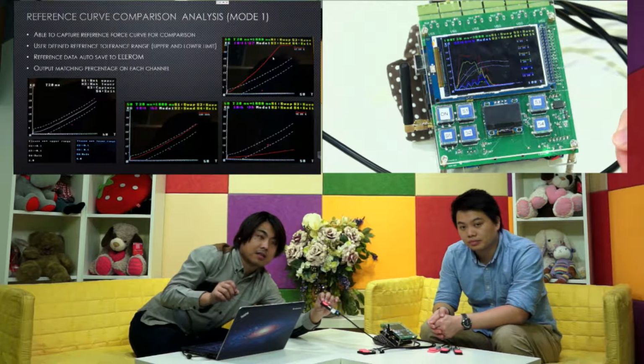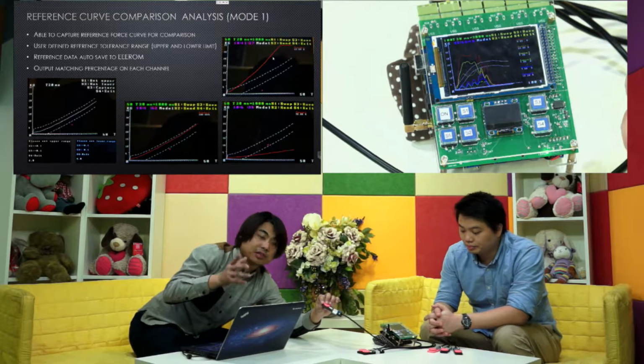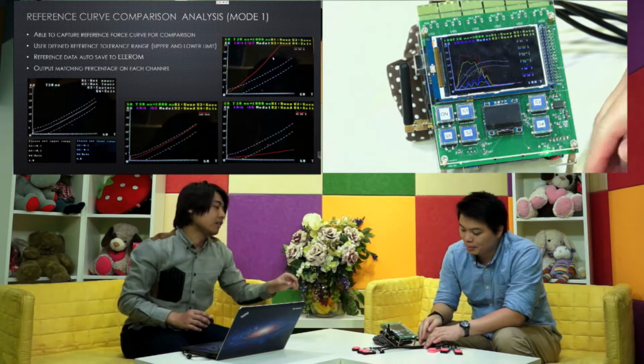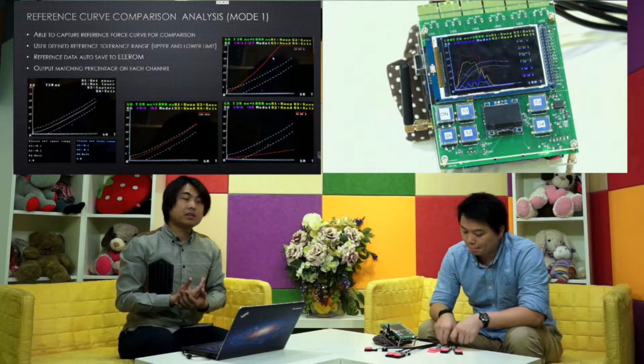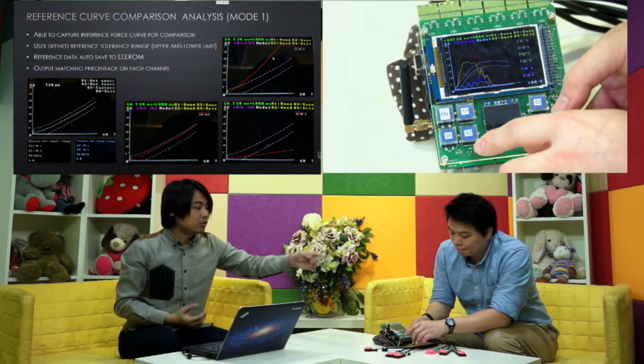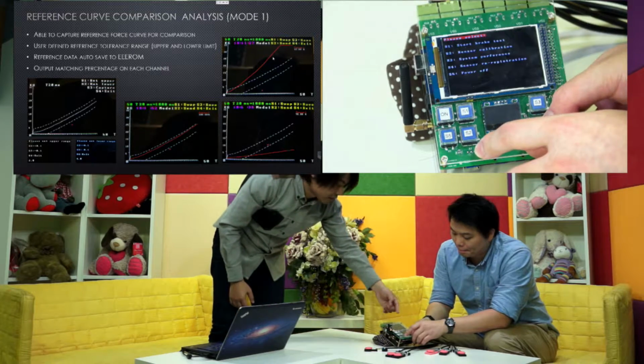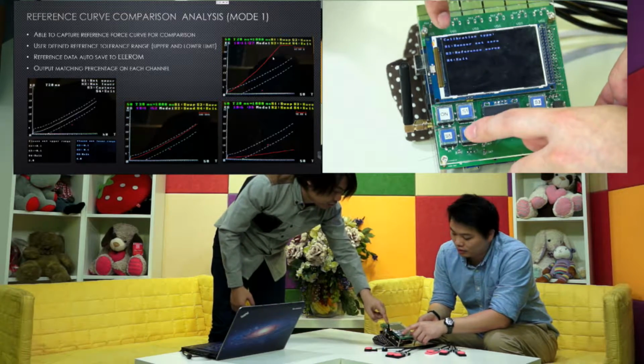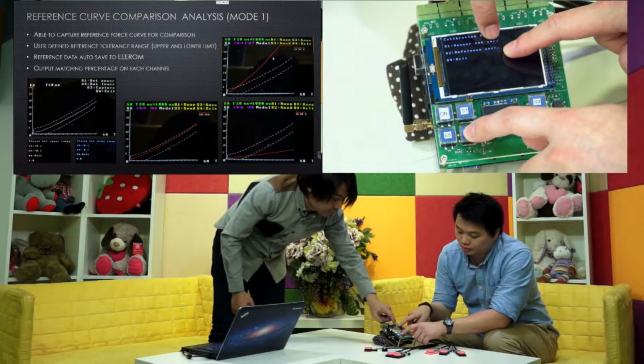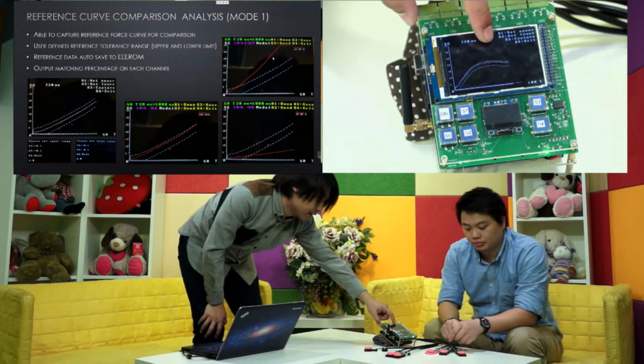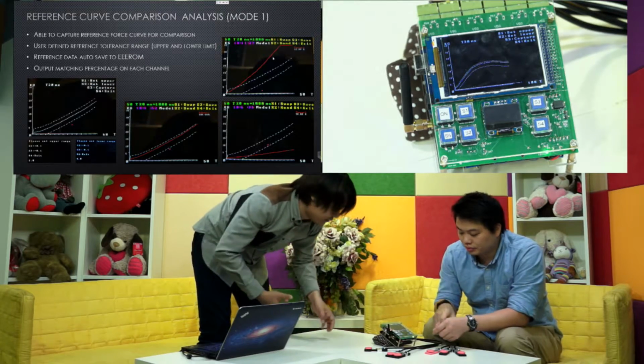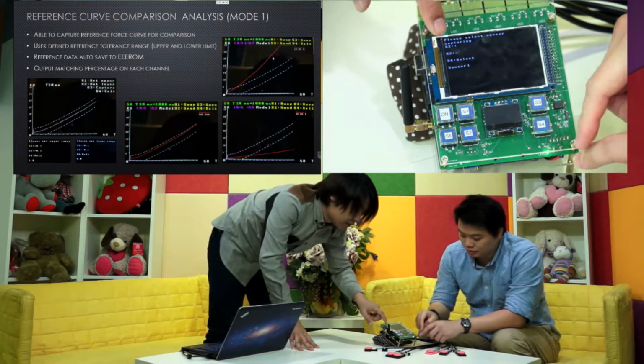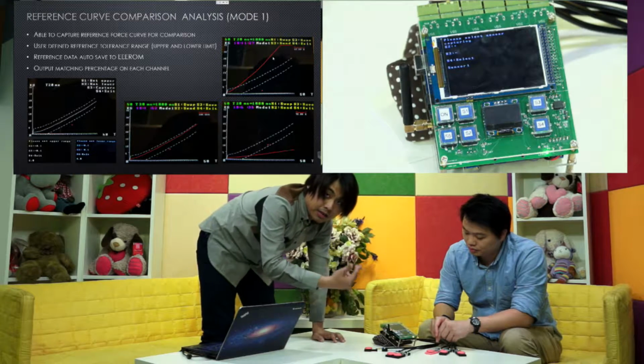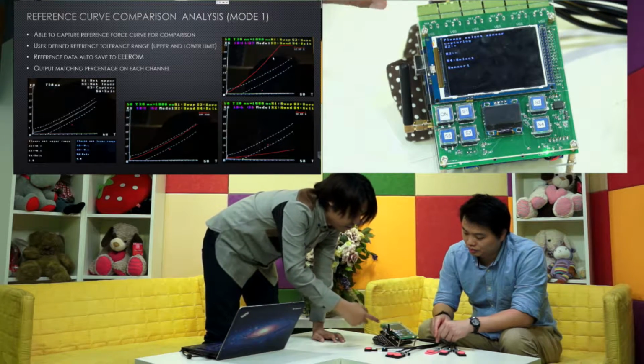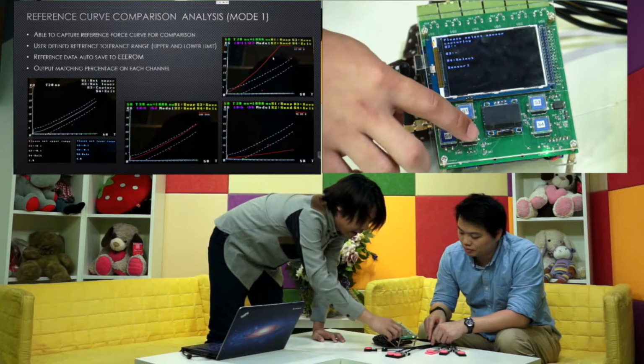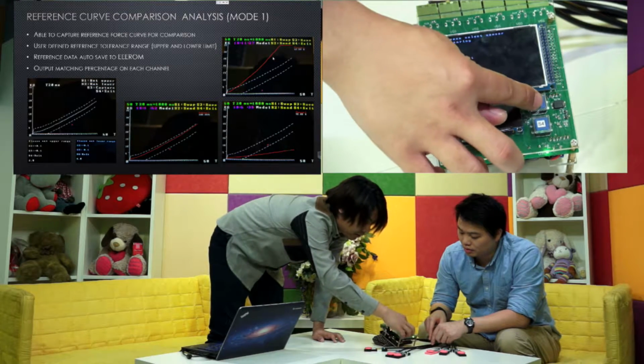It's difficult to decide how to apply the algorithm to the device, but comparing to the reference is very simple and easy. I'll show you how to do that. First, we need to take the reference sample. We go to sensor calibration again and choose the reference curve - this is from last time I took it for the device, but let me take it again for you. You can choose which sensor you want to take the force curve for - now select sensor 4, or maybe I'll use sensor 1.